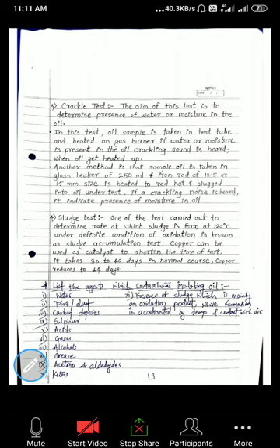If a crackling noise is heard, it indicates the presence of moisture in the oil. The rod is definitely red hot at that time, and when it is plunged, if the noise is heard, it indicates the presence of moisture in the oil.